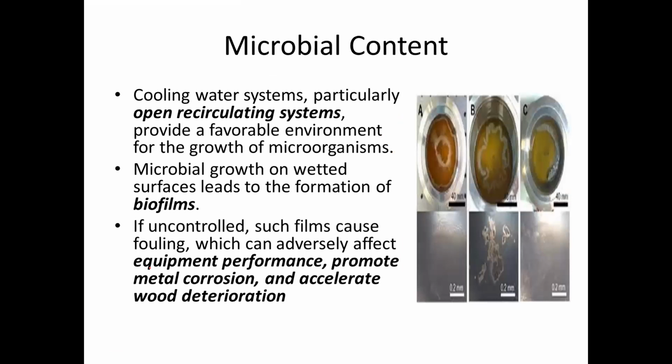And the last portion for our water analysis, water parameters natin will be microbial content. Cooling water systems, particularly open circulating systems, provide a favorable environment for the growth of microorganisms. Microbial growth on wetted surfaces leads to the formation of biofilms. And these biofilms, in the long run, pwede siya makakuha ng corrosion. Okay? So, ang biofouling, later discuss na siya.